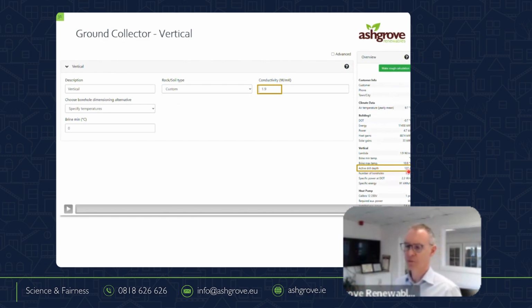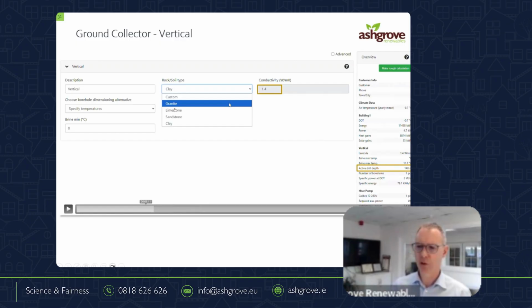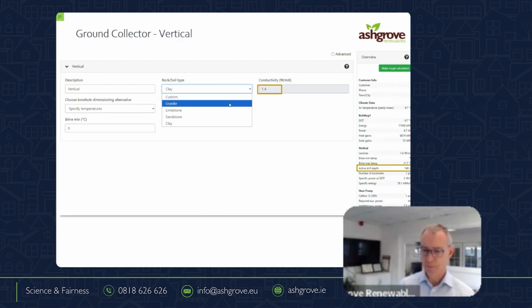So this tells us the amount of pipe that we need to have down into the wells. But importantly, if we go back here, if it's limestone, it's going to be much more pipe. If it's sandstone, something similar, clay and all the rest of it, they'll all perform differently. And if I'm trying to take, in a house, it's relatively predictable, even if I get it wrong. As you go up into the bigger stuff where I need 200 kilowatt or 500 kilowatt, I better know what I'm at. Otherwise, my only option is to oversize it. We know that's expensive, but at least it won't hit the running cost.